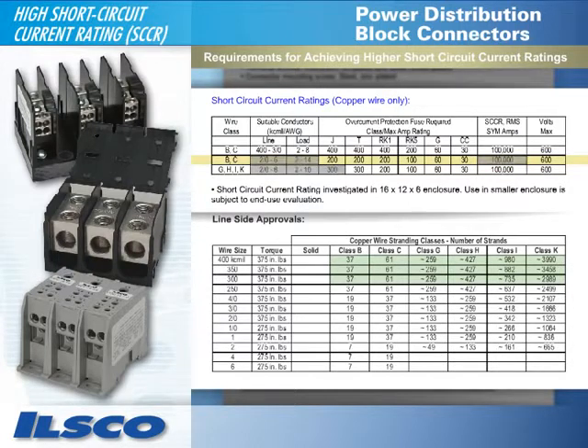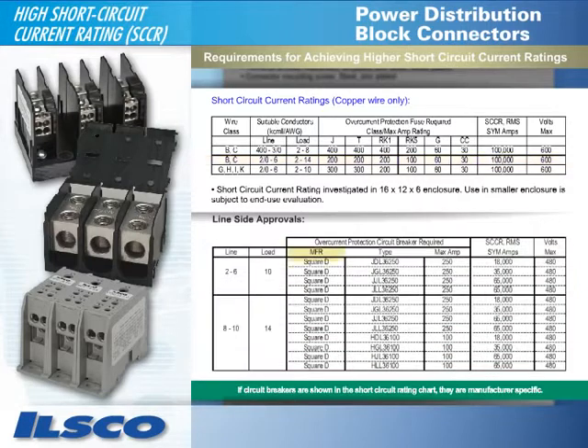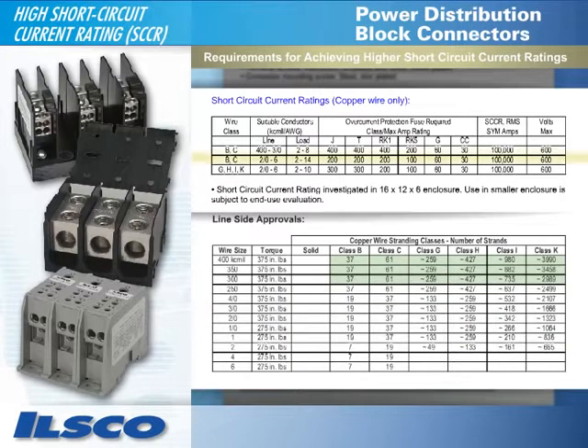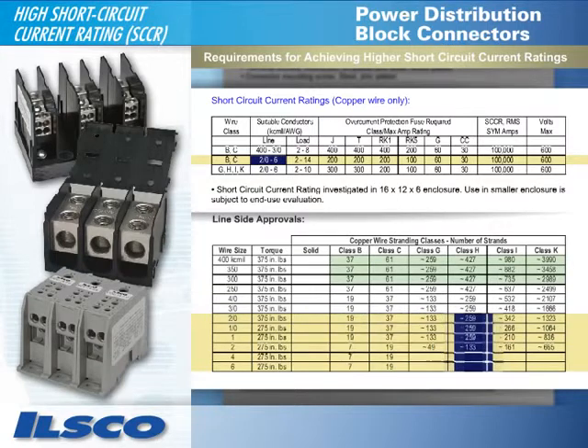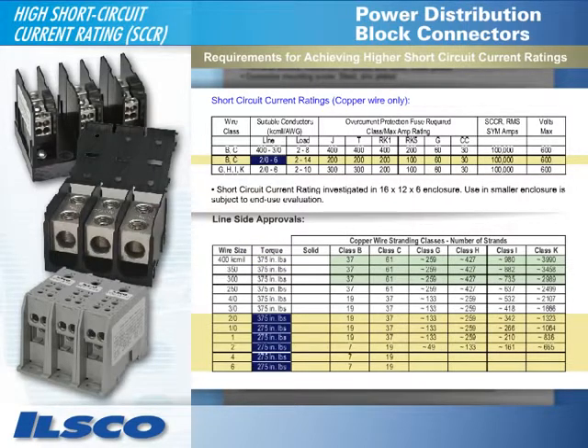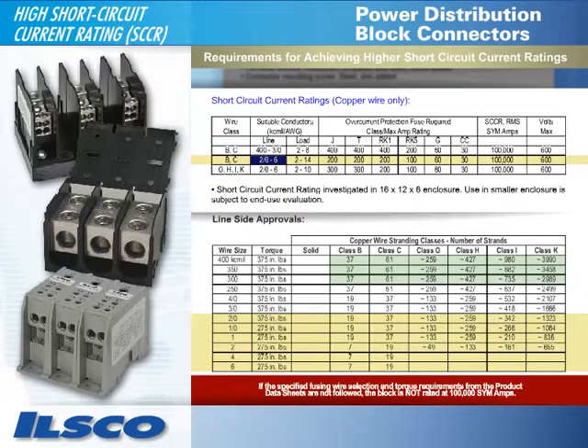As a side note, if circuit breakers are shown in the short-circuit rating chart, note that they are manufacturer specific. Looking again at the line-side approval chart, since the line-side conductor range in this example is 2-0 to 6, the approved number of strands for each wire class is indicated in the highlighted cells. The necessary torque for this range of wire sizes is indicated here. Again, if the specified fusing, wire selection, and torque requirements from the product data sheets are not followed, the block is not rated at 100,000 SYM amps — it is rated at 10,000 SYM amps.